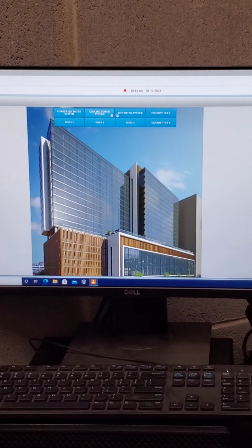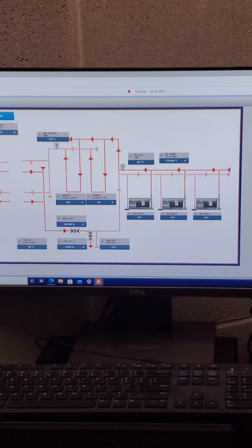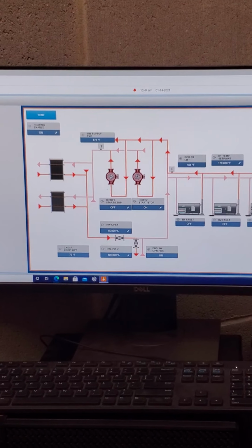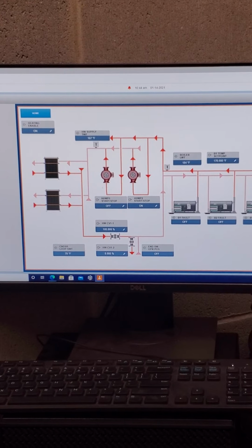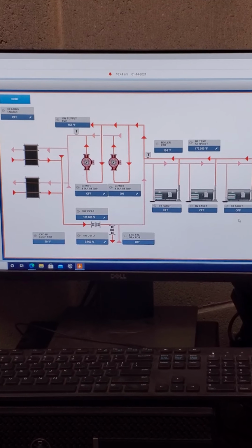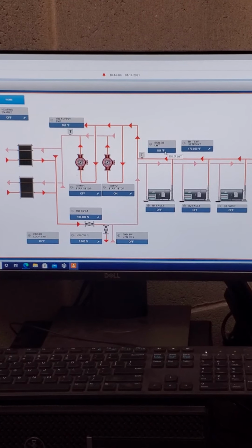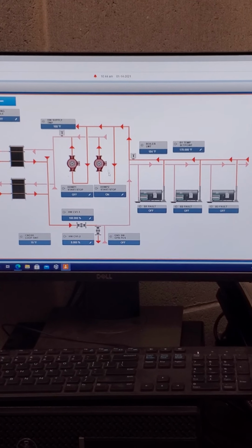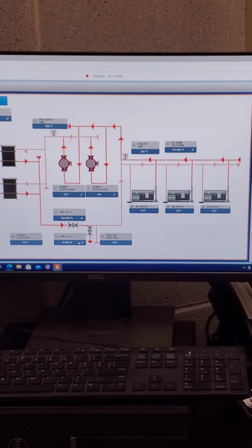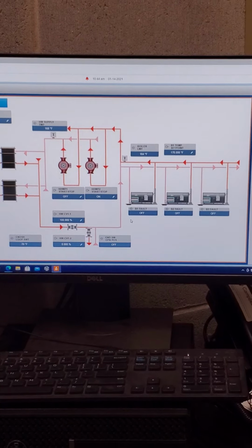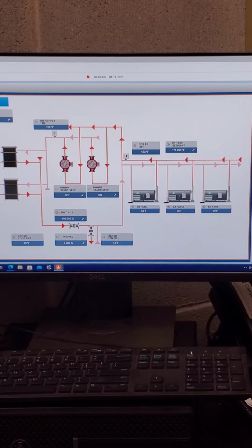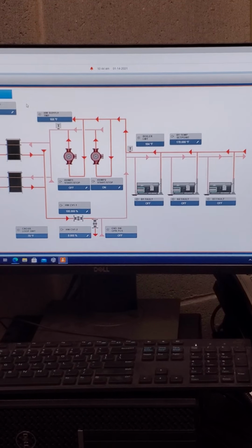Go back to hot water systems, take a look at this one. So you can see we currently have no boiler faults. We used to have some points on here for boiler command, but they're actually being controlled separate from our system, so we took those off. So we just see the fault conditions. You can see the water temps. You can see here that we have one pump running, one pump not, and you can see the status of the 6-inch and 3-inch valve that are up there to blend the water to get the right temperature. Currently heating is off because we're making set point, so that's all on this graphic here.